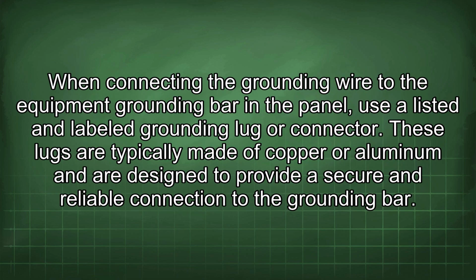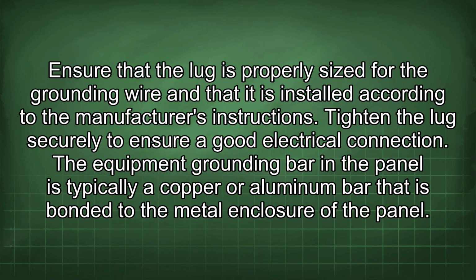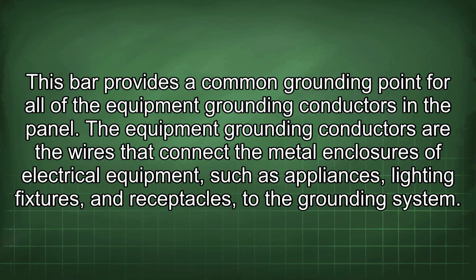When connecting the grounding wire to the equipment grounding bar in the panel, use a listed and labeled grounding lug or connector. These lugs are typically made of copper or aluminum and are designed to provide a secure and reliable connection to the grounding bar. Ensure that the lug is properly sized for the grounding wire and that it is installed according to the manufacturer's instructions. Tighten the lug securely to ensure a good electrical connection. The equipment grounding bar in the panel is typically a copper or aluminum bar that is bonded to the metal enclosure of the panel. This bar provides a common grounding point for all of the equipment grounding conductors in the panel.